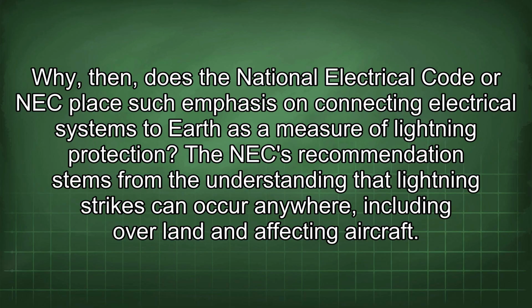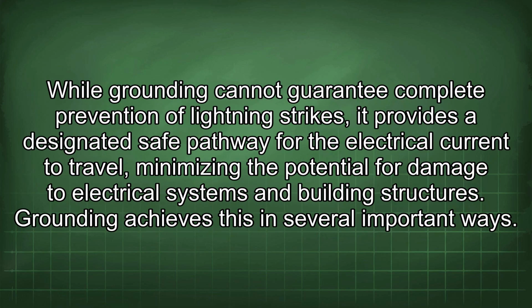Why, then, does the National Electrical Code or NEC place such emphasis on connecting electrical systems to Earth as a measure of lightning protection? The NEC recommendation stems from the understanding that lightning strikes can occur anywhere, including over land and affecting aircraft. While grounding cannot guarantee complete prevention of lightning strikes, it provides a designated safe pathway for the electrical current to travel, minimizing the potential for damage to electrical systems and building structures. Grounding achieves this in several important ways.